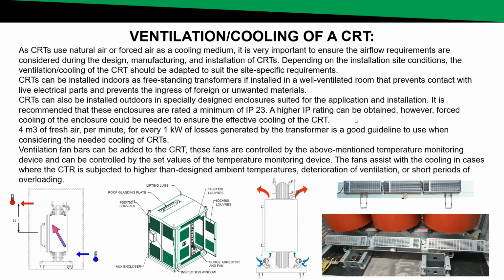However, as soon as you go higher than IP23, you usually need to use forced air cooling to ensure the ambient temperature in the enclosure is kept below 40 degrees Celsius. As a good rule of thumb, 4 cubic meters of fresh air per minute for every 1 kilowatt of losses generated by the transformer is a good guideline to use when considering the needs for cooling cast resin transformers.